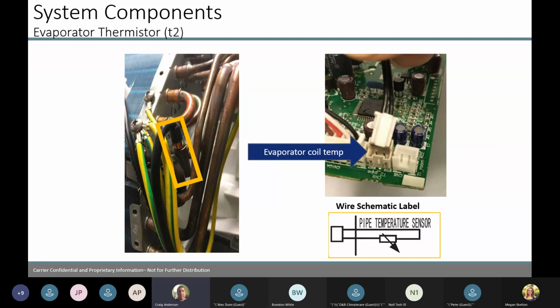Evaporator thermistor is a proving sensor. So once the unit turns on, our compressor turns on outside, this is reading, hey, I've got refrigerant going through it. This is the temperature of my pipe. This is what I'm going to tell the EE valve to do outside, because we're a modulating unit. So it's going to work with the EE valve to modulate the amount of freon that's going through the unit. If it's not reading properly, if we're undercharged or overcharged, then it's going to determine how the unit is going to operate. So all that is a prover switch to tell us gas is going through the unit and how much.